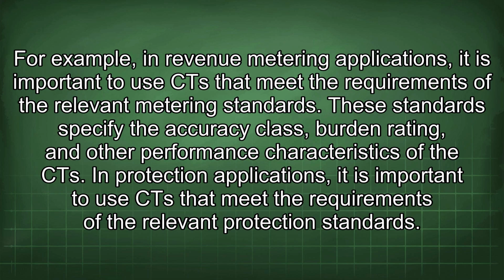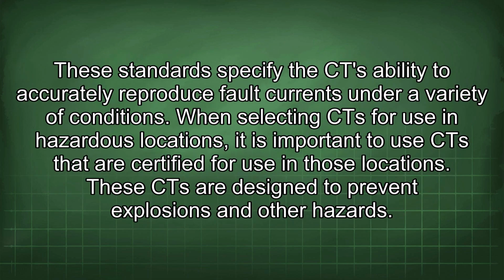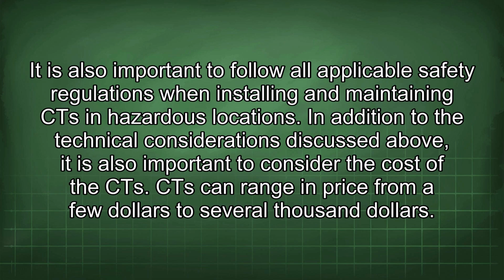In protection applications, it is important to use CT that meet the requirements of the relevant protection standards. These standards specify the CT ability to accurately reproduce fault currents under a variety of conditions. When selecting CT for use in hazardous locations, it is important to use CT that are certified for use in those locations. These CT are designed to prevent explosions and other hazards. It is also important to follow all applicable safety regulations when installing and maintaining CT in hazardous locations.